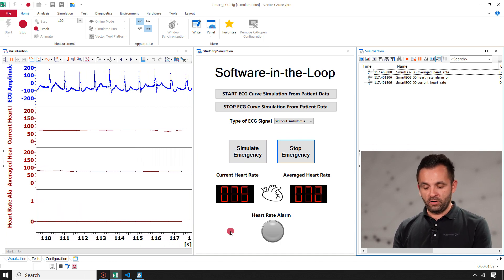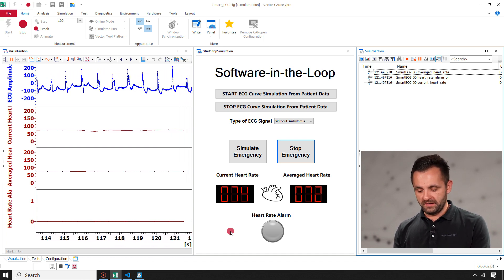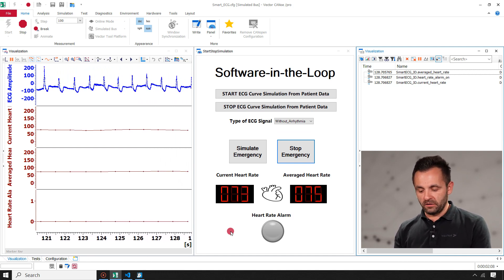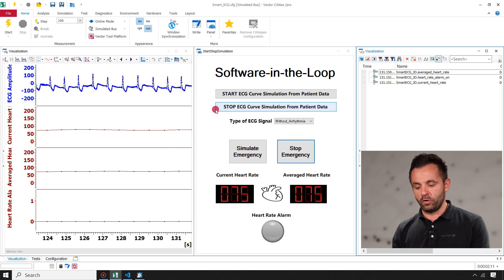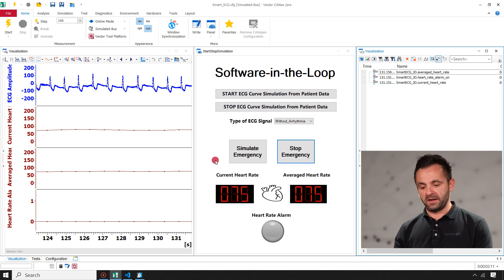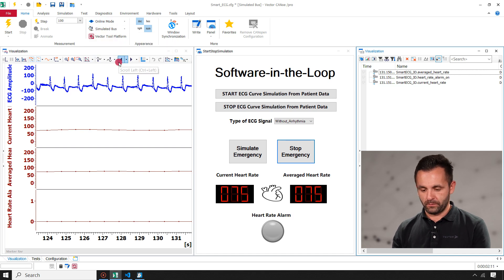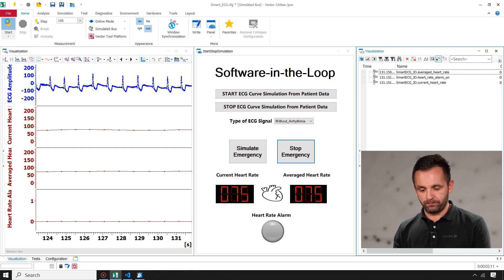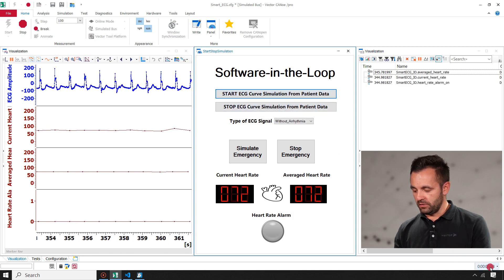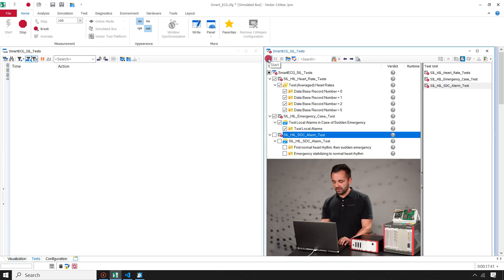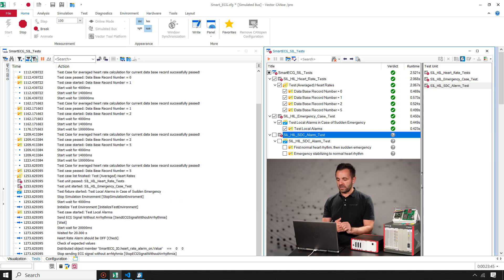What I just demonstrated can also be fully automated at a later stage of development by automated tests designed in VTest Studio. However, these tests can take quite a long time, so we want to speed them up — which we can only do in the Software in the Loop case. In this specific example, I can speed them up by a factor of 100. Starting the measurement again with time running 100 times faster than real time, I switch to the Tests tab and start the selected tests. You can see that they all passed, so our ECG device behaves as intended.